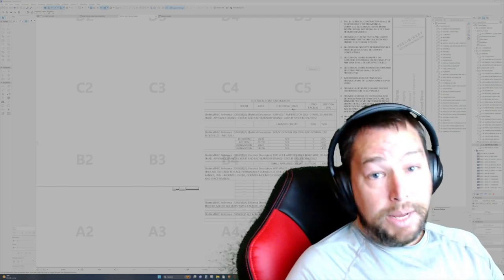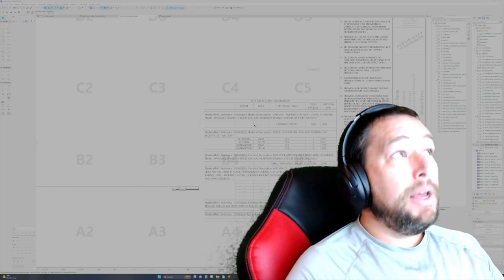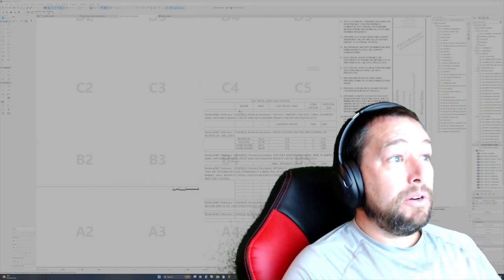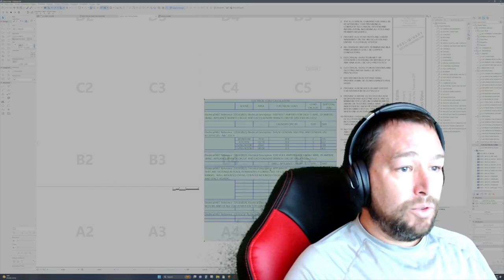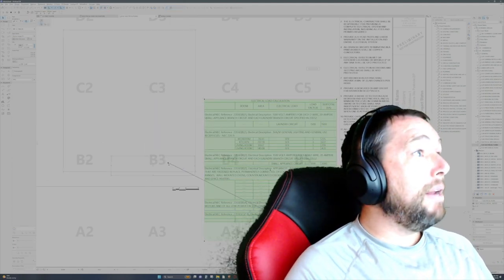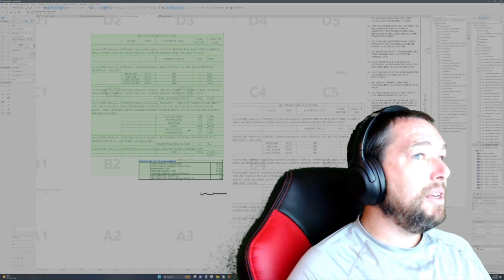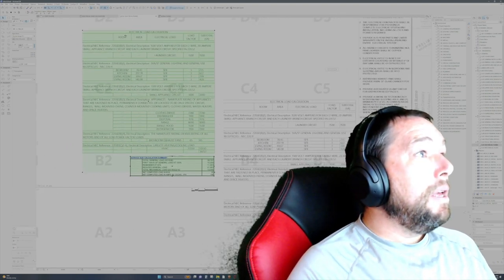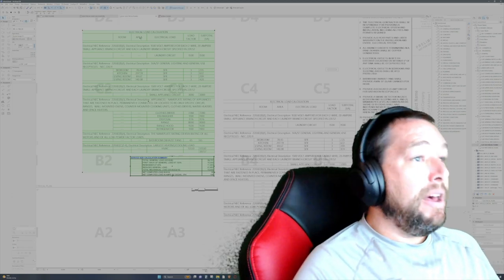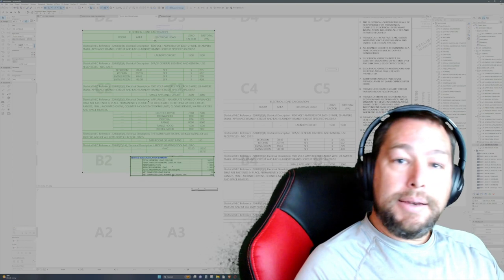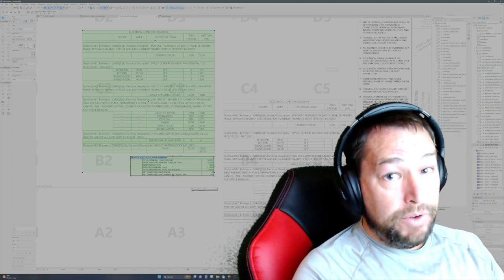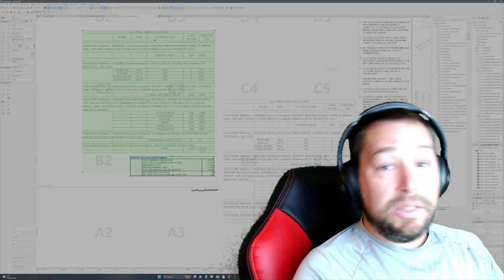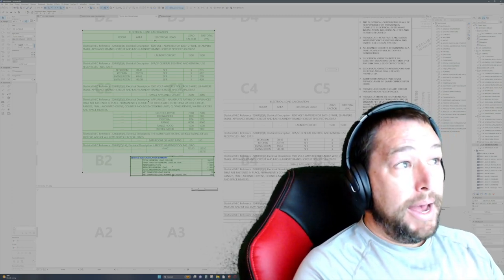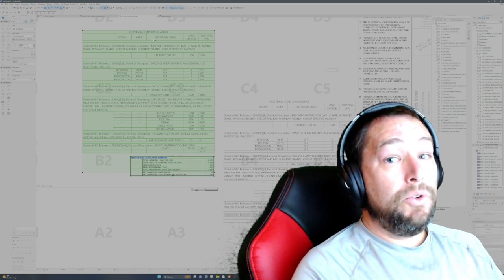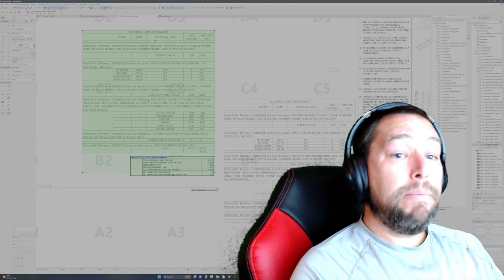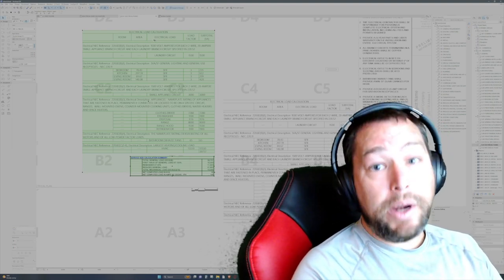I've worked up a methodology, and as you can see on this screen, this is an electrical load schedule. Let me move it over so it's easier to see. The idea is to have a load schedule that takes into account the square footage of the building. In this case, it's a single family residence, and we want it to automatically calculate based on square footage, because the NEC 2020, the current electrical code for Utah, again your mileage may vary, specifies a certain volt amp requirement per square foot.